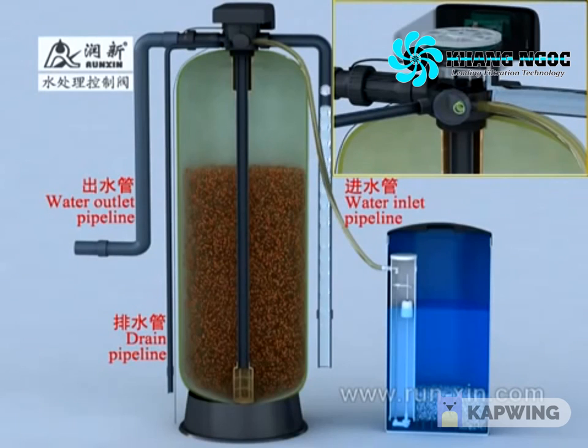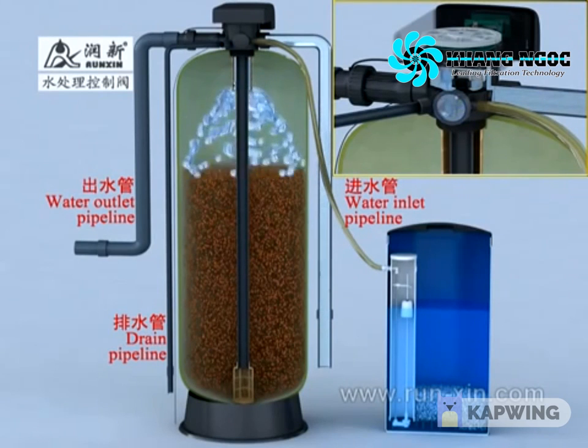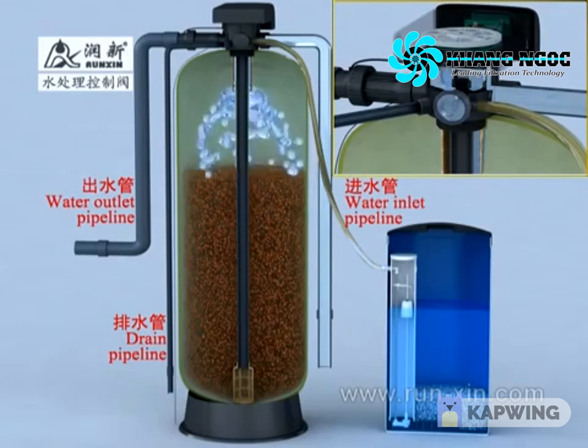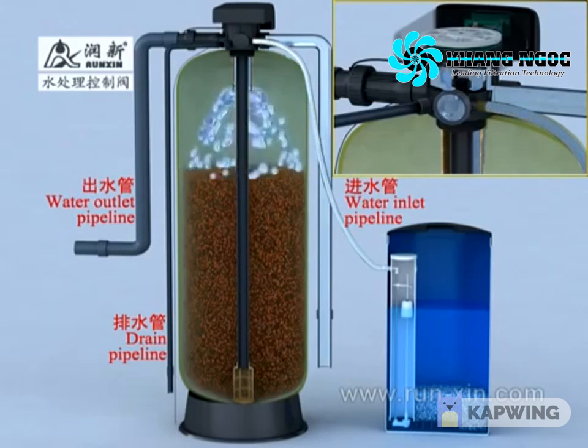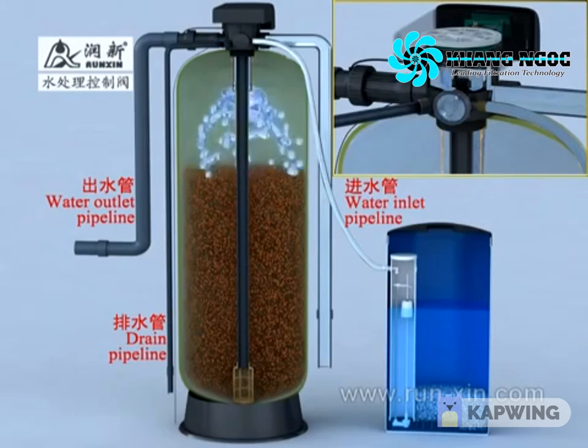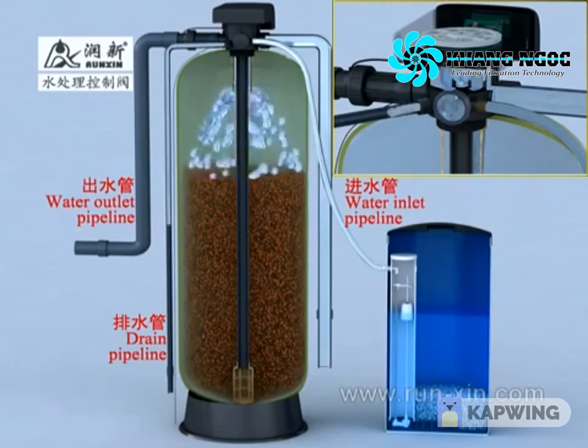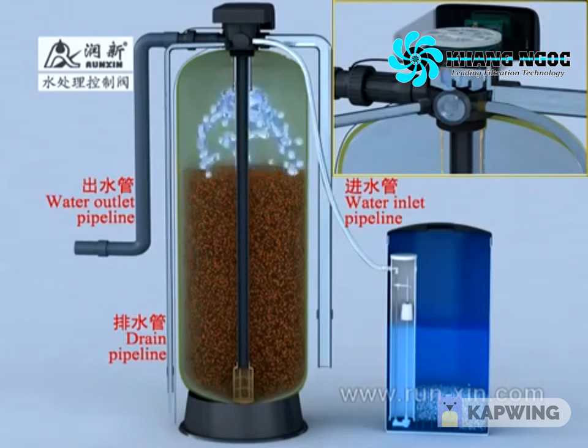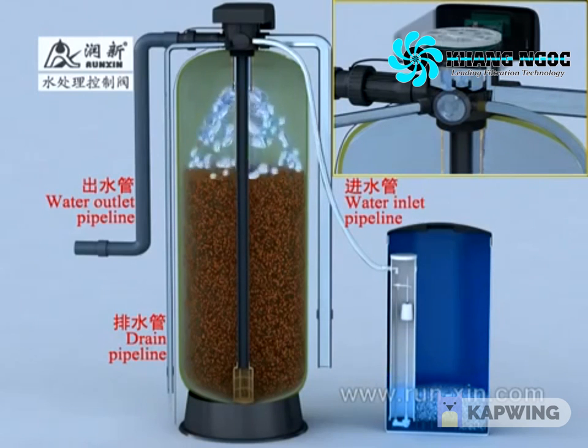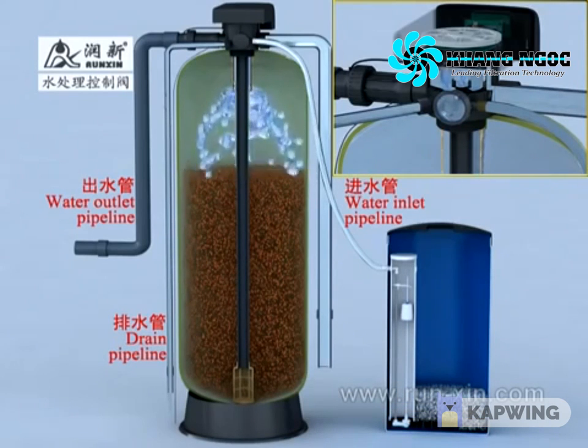Raw water flows into the control valve through the water inlet, passes the valve core to the injector inlet, and flows quickly to the injector outlet, which produces negative pressure, so that the brine is sucked from the brine tank through the brine line connector to the valve, then to the tank. The brine goes down through the resin layer, through the bottom strainer to the riser pipe, then upward to the valve body, valve core, and finally flows out from the drain outlet.